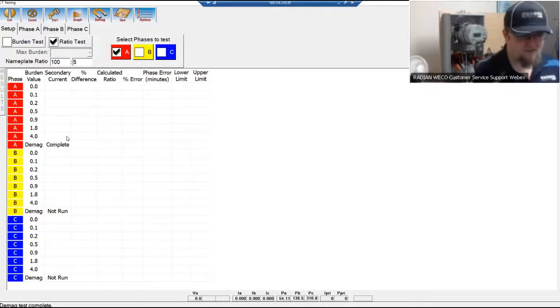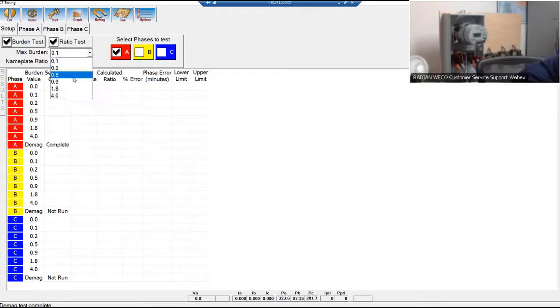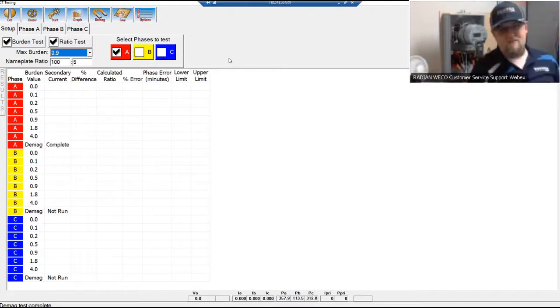You can choose the max amount of burden, and you can also tell the RW what types of CTs you're testing. So with these, like I said earlier, these are 100 to 5 CTs. So I've got 100 to 5 in as the nameplate ratio of these CTs. And then if I go ahead and check burden here, I can choose anywhere between 0.1 ohms to 4 ohms. For the test I'm going to do today, I'm going to add 0.9 ohms of burden.